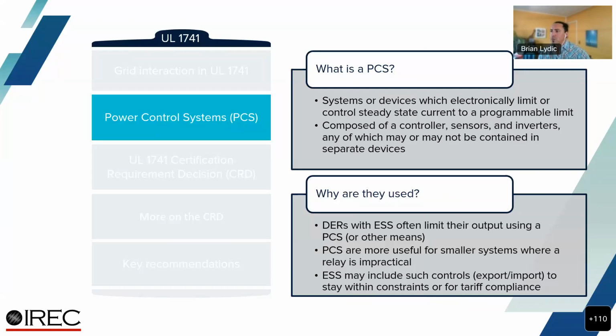One way these have been used, and are currently used, is for tariff compliance. Net energy metering tariffs generally don't allow you to import power from the grid into an energy storage system and then export that and get net energy metering credit for it. So often, one way for a utility to verify that you're not doing that is to constrain the energy storage system from either importing from the grid or exporting to the grid. That's one way these systems are used today.